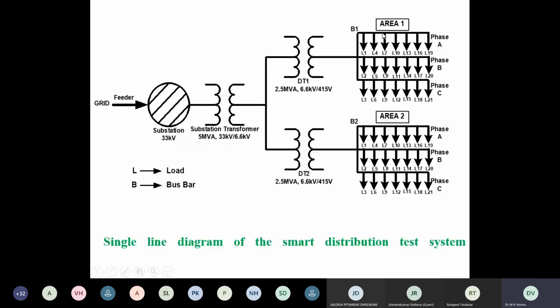Similarly, we have different feeders. This is the phase A feeder, phase B, phase C. If in any of the phases the current exceeds its limiting value, that is, there is overcurrent in a certain phase, that overcurrent is detected by the local controller at the distribution transformer. Based on the overcurrent protection algorithm, some of the loads are disconnected to bring the current within the limiting value. After some time these are reconnected, and again it is checked whether there is still overcurrent or not. If there is, then again some disconnection is done. All these algorithms are run at a regular 1 minute interval. And if there is some theft somewhere, that theft is also detected in different areas.